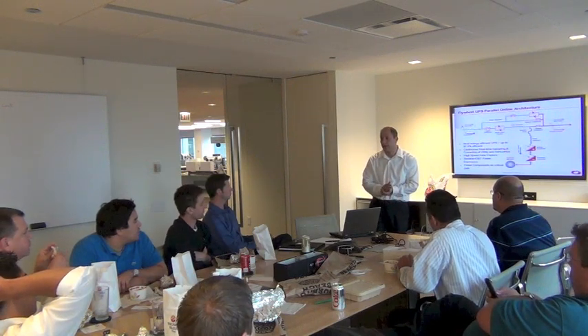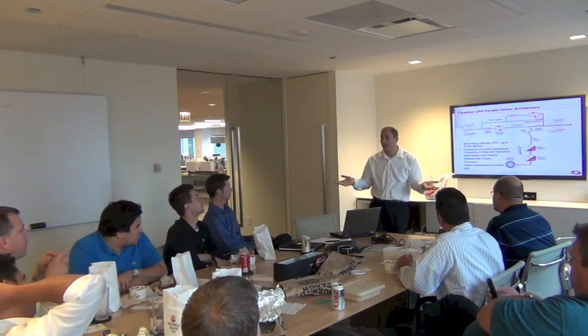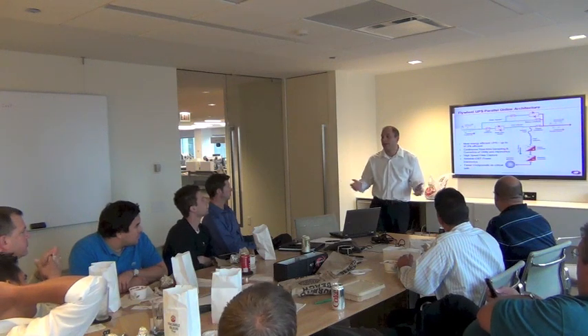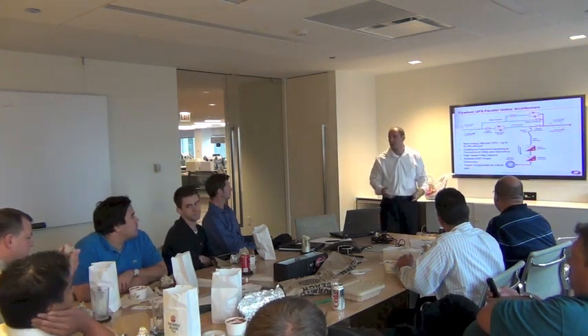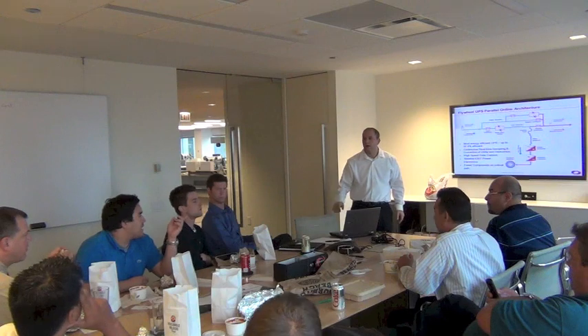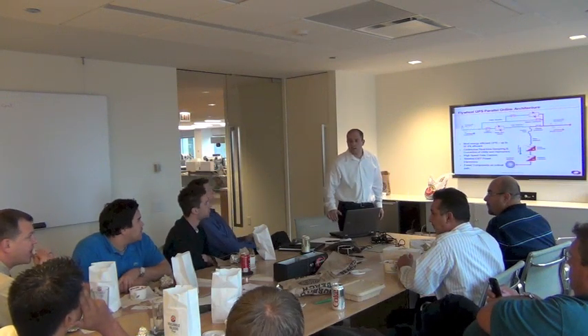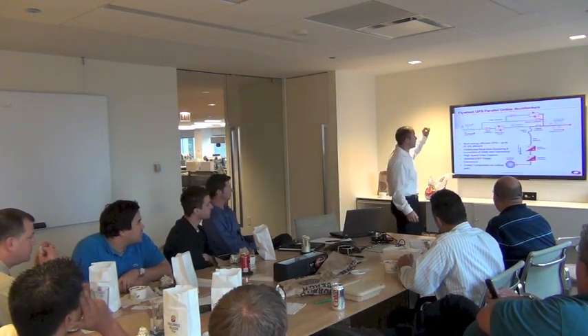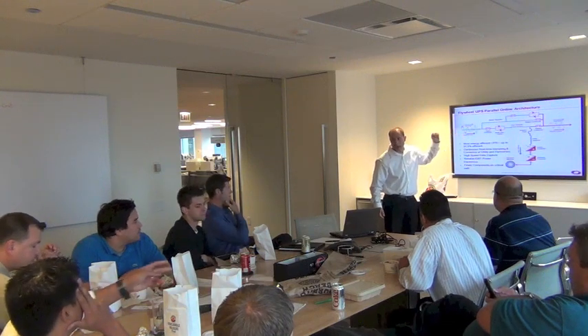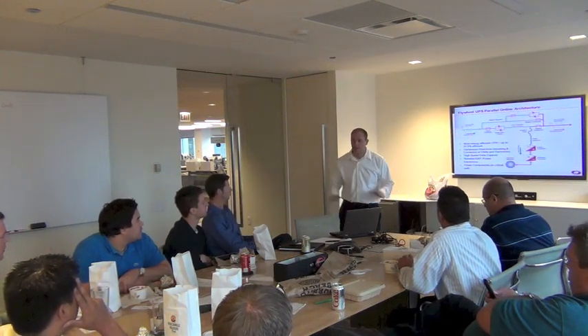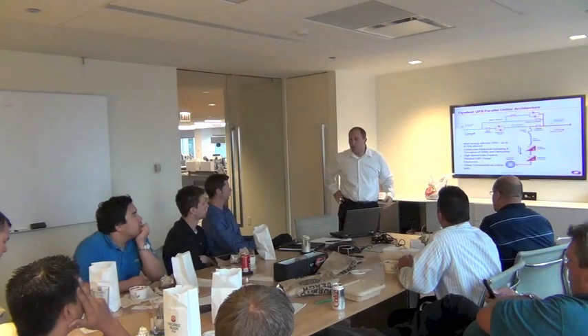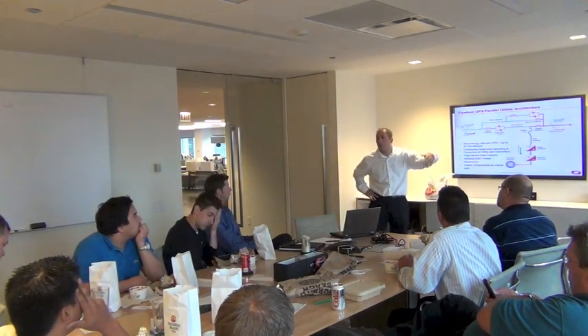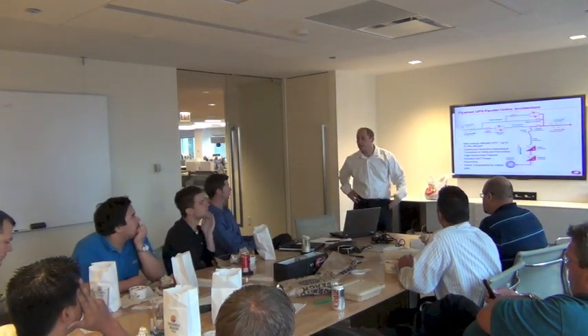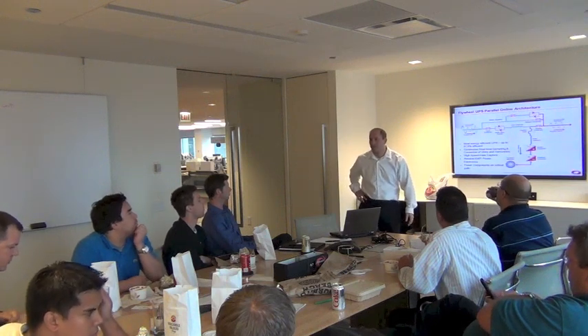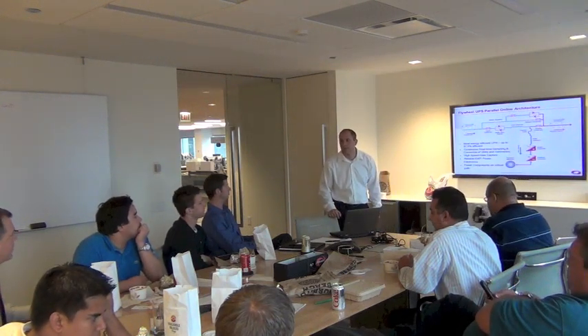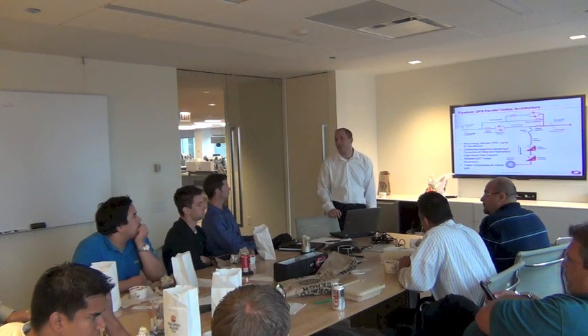And typically, ride-through time is very linear. So if you want to know how much time you get at 50% load, you get 14.5 seconds at 100% load, about 28 seconds at 50% load, or 52 to 56 seconds at 25% load. And also, typically, how are these systems grounded? We always require a grounded Y input. Okay. And we're always grounded on the output, whether we're in normal online mode or discharge. Do you work with high resistance ground systems? Yes, absolutely. It's an option on our equipment.